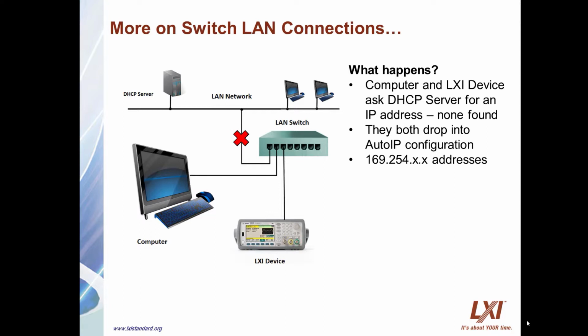If a LAN device has no connection to another LAN device, it will recognize no connection and automatically come up with an IP address of 0.0.0.0 and indicate with a LED or a message on its front panel display that no LAN connection exists, which refers to a LAN status fault in the LXI specification.